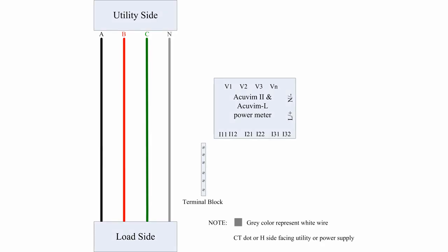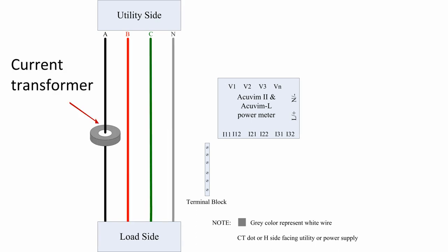First of all, a current transformer should be added to each phase line, which will step down the current to desired levels. In this diagram, a donut or solid core CT was added to phase A, with the black and white wires sticking out.